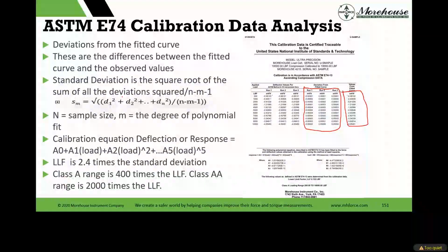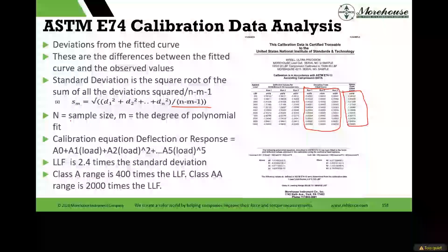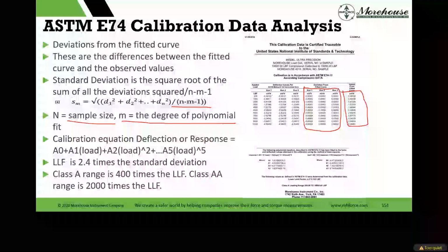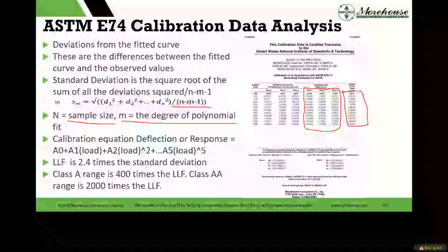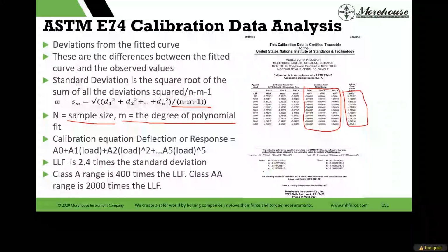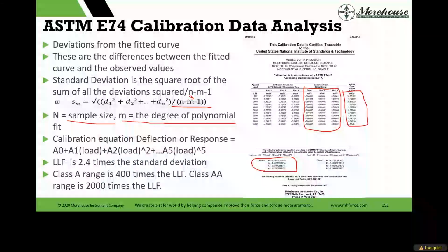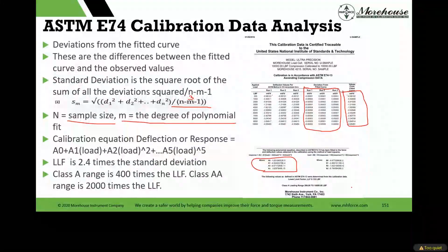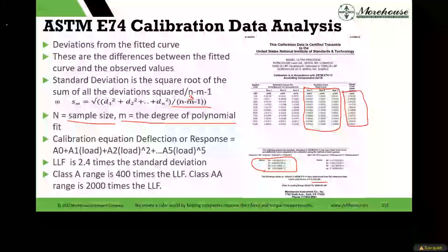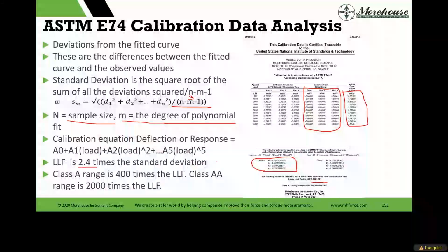Standard deviation is the square root of the sum of the squares, over n minus m minus 1, where n is the sample size, m is the degree of polynomial fit. And the penalty on this is if I fit to like a third degree here, that my m becomes a 3. That makes my denominator smaller, which gives me a larger number when we calculate this lower limit factor. At the end of all of this, ASTM was written so you multiply this standard deviation that then we convert to whatever unit we're in. We multiply it by 2.4, which gives me this. And I think I jumped the gun earlier.